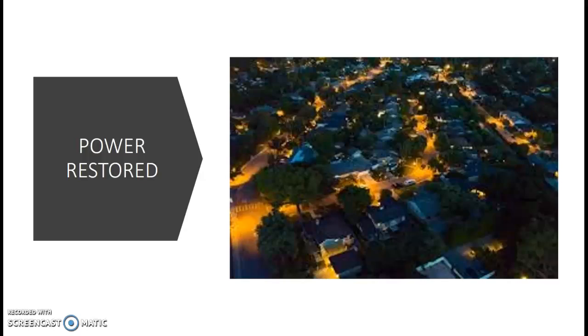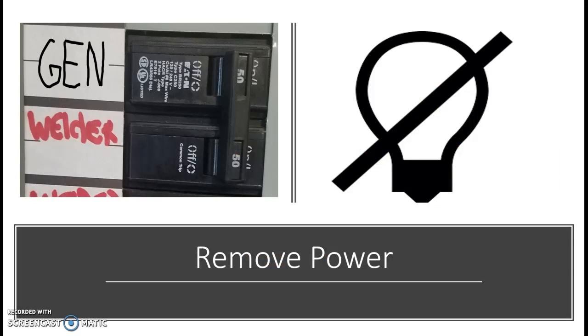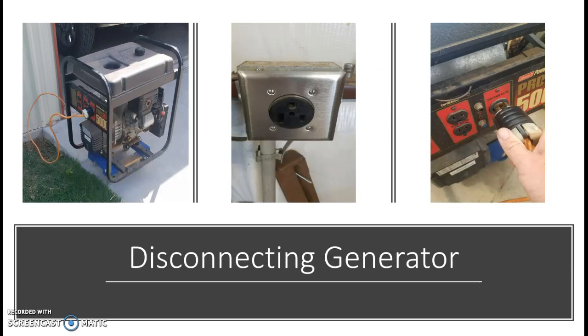When power is restored, we're going to go ahead and go to that generator circuit breaker in our circuit breaker panel, and we're going to turn it to the off position. You will lose power to the home at this time. Next, we're going to turn our generator off. We will disconnect our plug from our designated outlet, and then we will remove the plug from the generator.